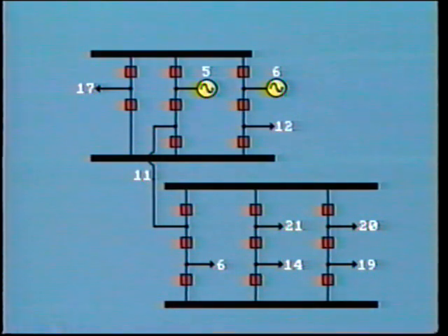I suppose it's inevitable that this perfect world cannot exist 100% of the time. And misoperation does in fact take place due to protection scheme failure. Let's look at a few case histories of this. In this sample, line 11 developed a ground fault, and this was cleared correctly by tripping the breakers at both ends of the line.